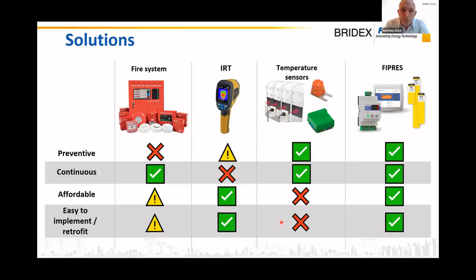And then this sticker will present different levels of temperature, the thermodots, which are 50, 70, and 90 degrees here on the picture. And whenever you reach 70 degrees, or 50 degrees, the thermodot will turn black, and this is non-reversible. Then at a temperature of 100 degrees, the sticker will release gas, and this gas will be sensed by an electronic device that is located within the same compartment as where the stickers are, and that will trigger an alarm.